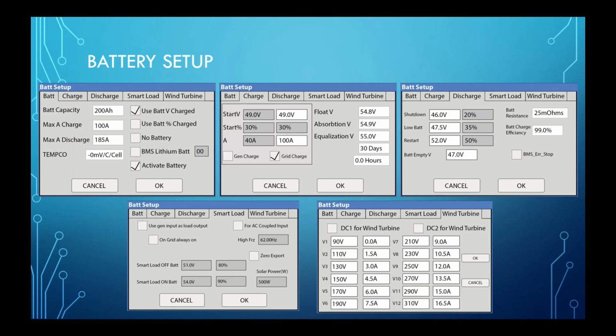On the left-hand side, you have the settings for your grid charge and gen charge. If you are able to charge from the grid, all you need to do is put a check mark. Gen charge is important if you're trying to use the two-wire start feature. The start percentage is the point at which the SoC has to drop below that value for longer than 30 seconds, and then at that point, the two-wire start will activate. And then the amps is just the amount of amps that you're able to pull from the generator for charging.